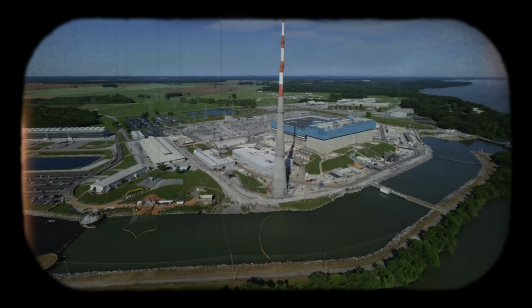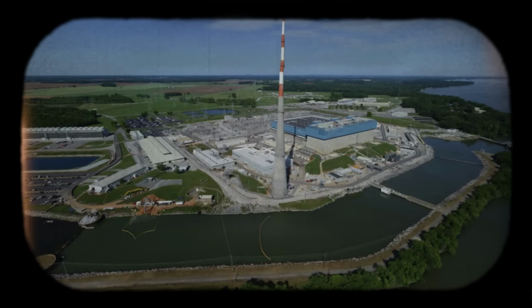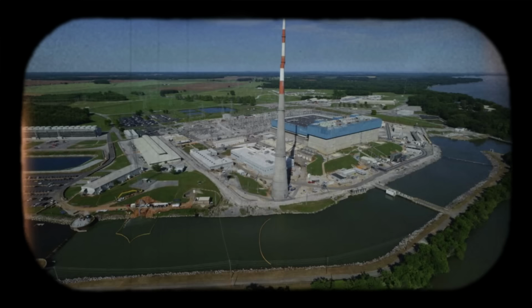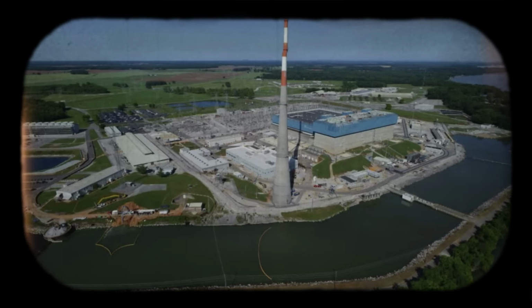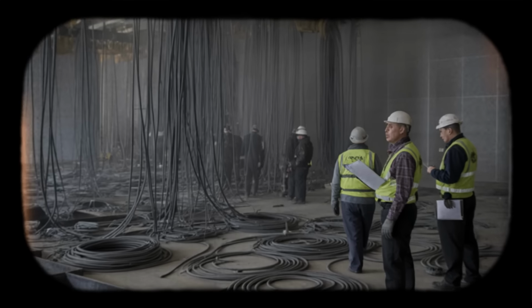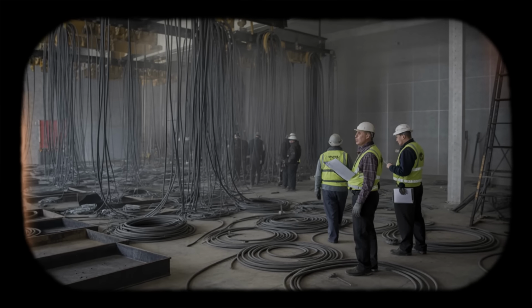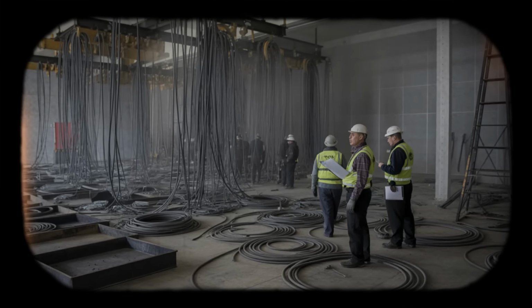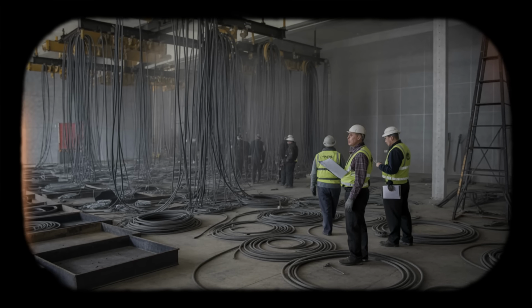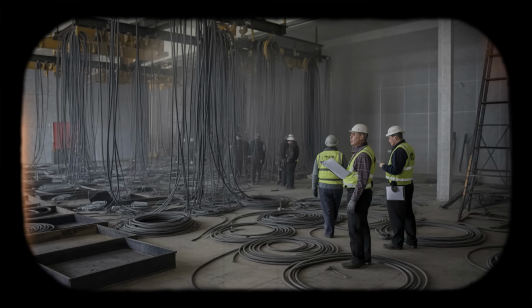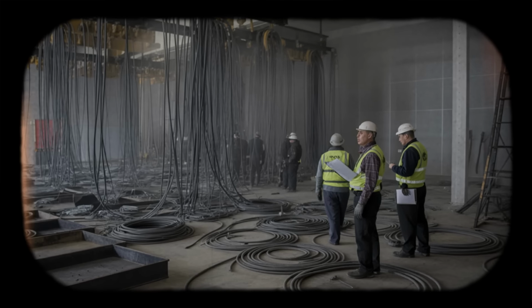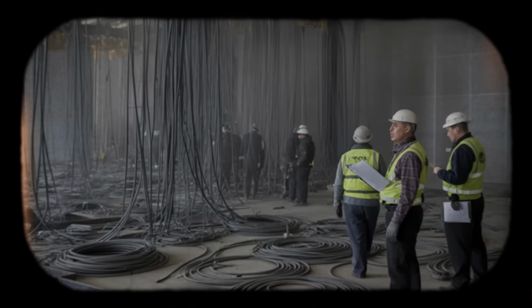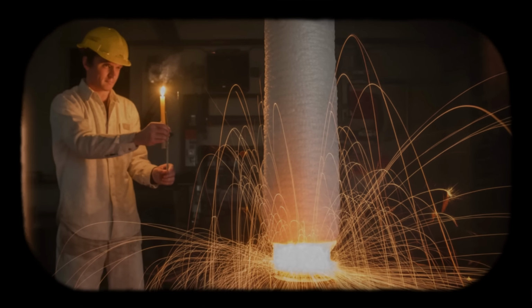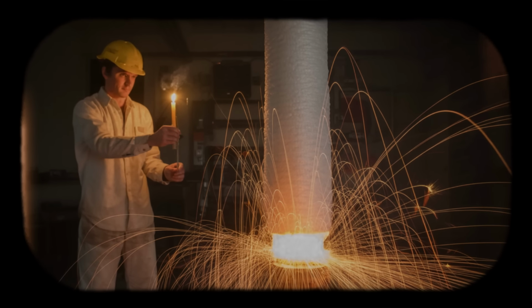But beneath the control room floor, in the cable spreading room, circuit bundles routed through penetration 5 are beginning to short. Heat from the spreading fire softens insulation. Conductors that should remain electrically isolated come into contact. Signals degrade. Some circuits fail entirely. Others produce intermittent, unpredictable behavior. The cables passing through penetration 5 include damper control circuits, alarm system wiring, and instrument power feeds. All of these systems share common routing because they all pass through the same wall penetration on their way to equipment in the reactor building.